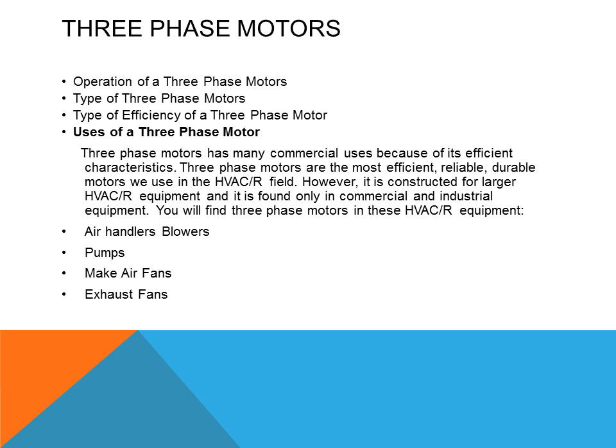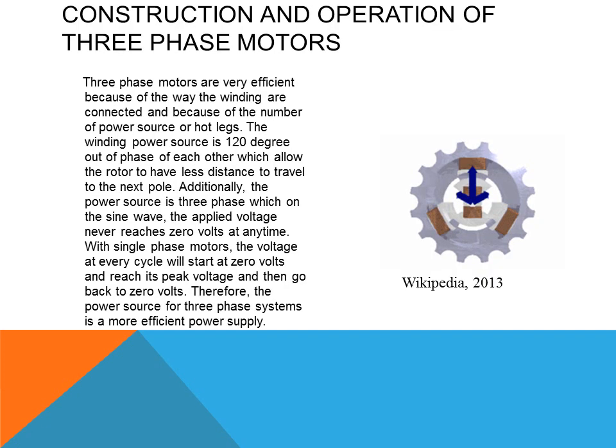Three-phase motors have many commercial uses because of their efficiency characteristics. They are the most efficient, reliable, and durable motors used in the HVAC field, constructed for larger HVAC refrigeration equipment found only in commercial and industrial settings. You will find three-phase motors in air handler blowers, pumps, makeup air fans, and exhaust fans. Three-phase motors are very efficient because of the way the windings are connected and the number of power source hot legs they have. The winding power source is 120 degrees out of phase with each other, which allows the rotor to have less distance to travel to the next pole, giving it additional torque and strength.